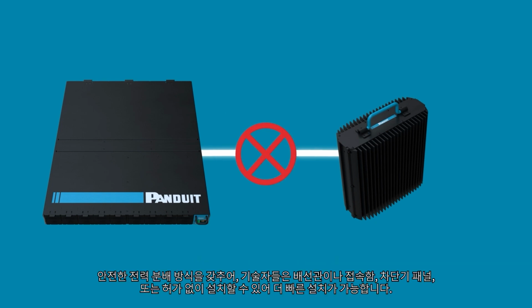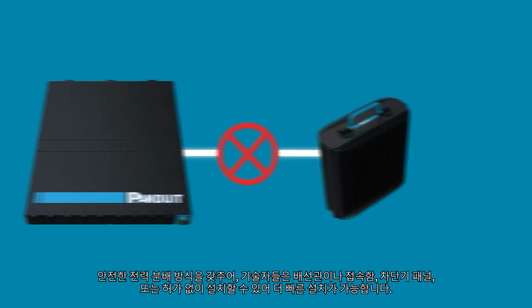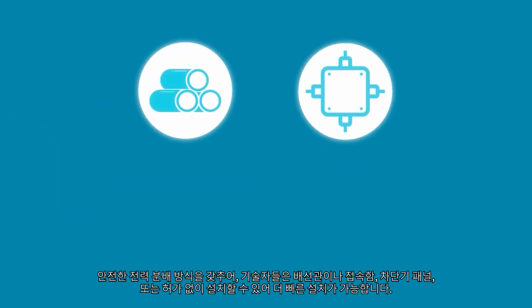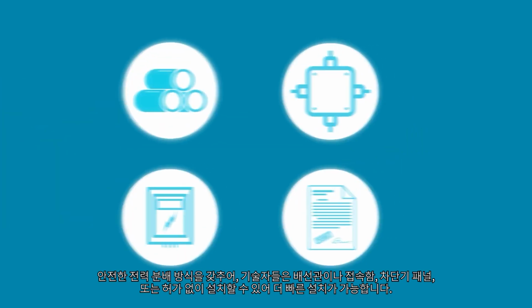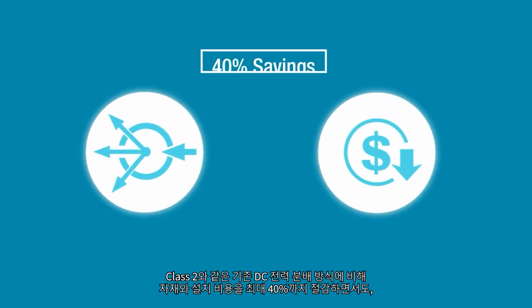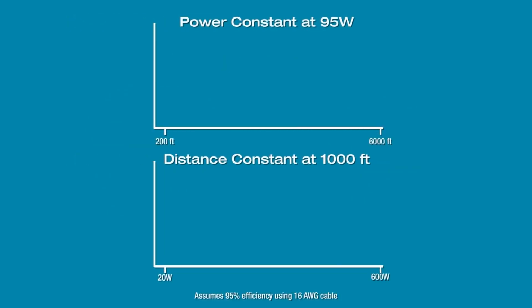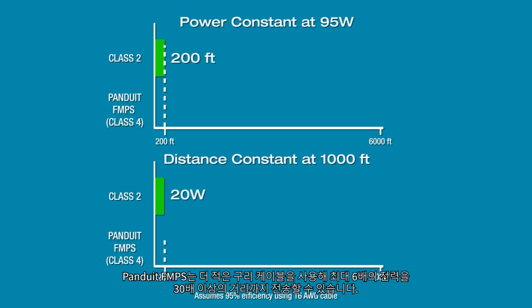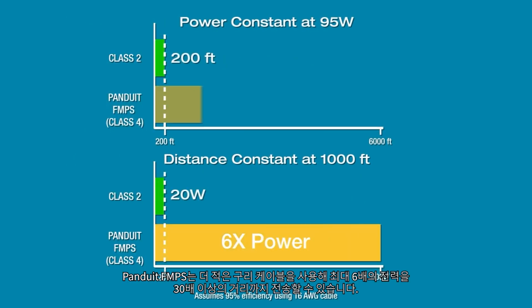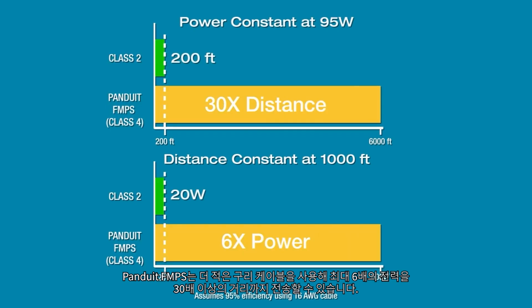Its safe power distribution allows technicians to install it with no conduit, junction boxes, breaker panels, or permits, making it faster to deploy while saving up to 40% on material and installation cost. Compared to traditional DC power distribution, such as Class 2, Panduit FMPS can deliver up to 6 times the power over 30 times the distance while using less copper cable.